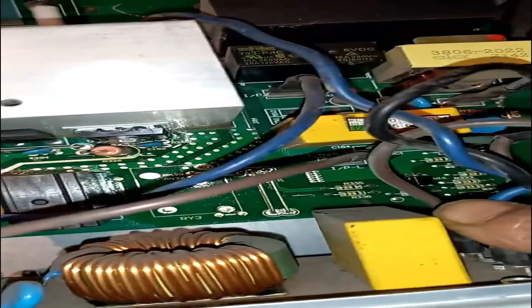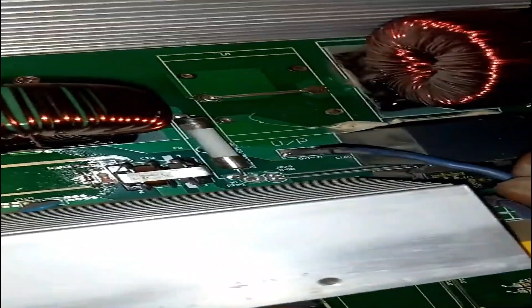This input voltage comes to the filter. Then from the filter there are two parts. One part goes to the main board and another goes to the charger card. See, this black is negative and brown is positive. You have to check where plus or minus is marked, and put the cable accordingly. And from there the output voltage comes, OP plus V, that means positive output, and OP minus V, that means negative output. So you have to check that and then go to the main board side.